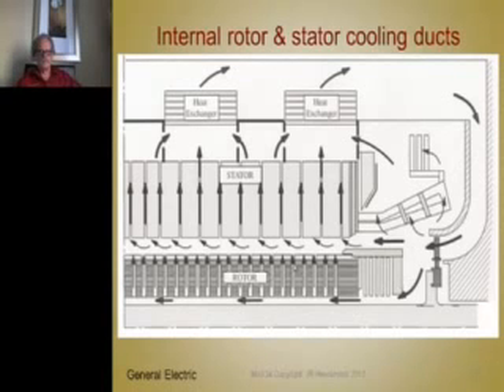I guess this is a different sort of view. This is an induction motor rotor or a synchronous wound field rotor with passageways through the rotor and the stator, and so you've got a heat exchanger here where you're taking the heat out of the cooling media, and it's recirculated, pressurized to go in the air gap and in the ID passages in the rotor. Here's a shaft, and there's passageways there that it's directed down into there and here, and there's some vacuum pump out here that causes a circulation, goes through heat exchangers to cool the motor. These are how you cool great big machines, and I think some of these things have to be applicable to smaller machines.